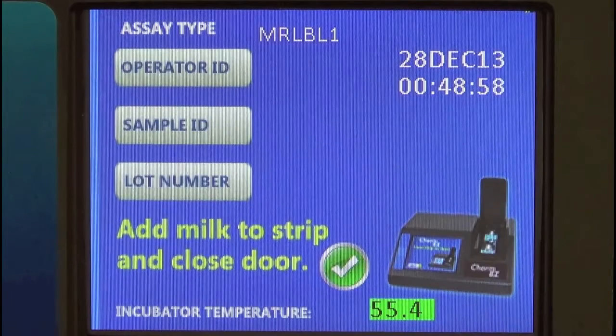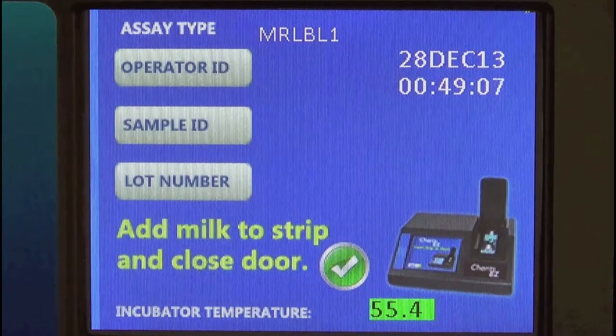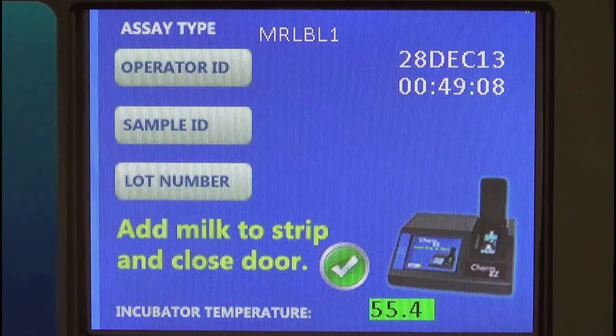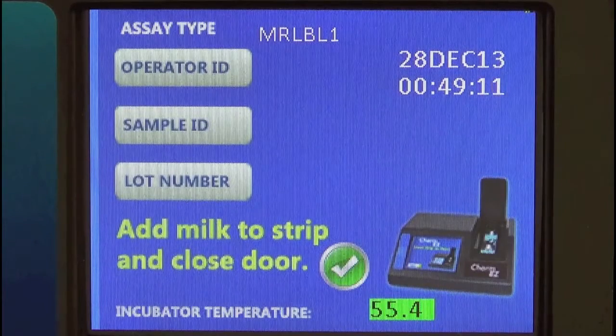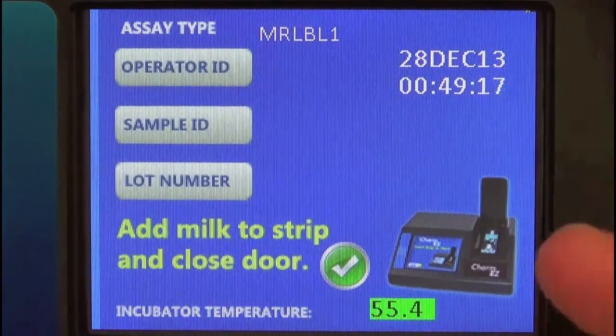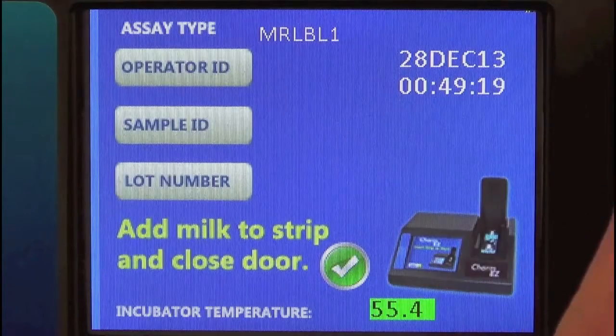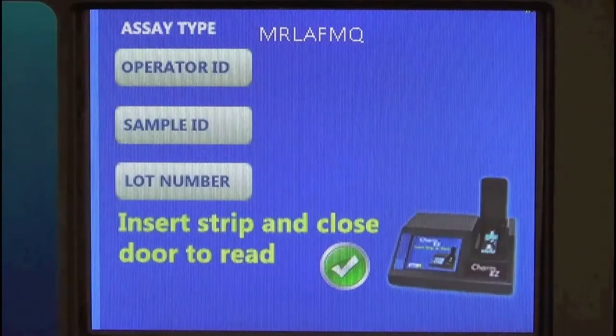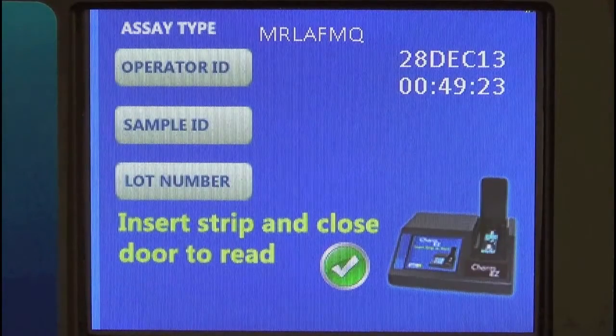For high volume customers, this saves them time, but it also utilizes the color sensor feature of the EZ-Reader. So if somebody did enter a different strip, say in this case a light blue Emerald AFMQ strip, the reader would still automatically sense that the strip color was different and load the proper calibration values.